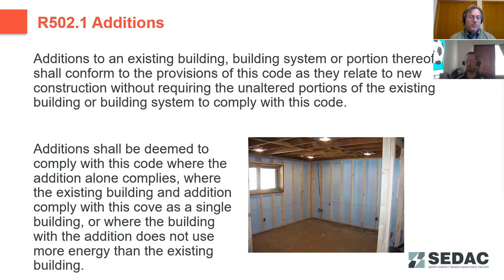You can do prescriptive compliance for the addition and test it independently, as far as meeting R-value requirements, making sure the envelope is sealed, making sure any new ductwork is sealed. But again, additions to existing structures do not have a requirement for air leakage testing or duct leakage testing, the duct leakage testing being an Illinois amendment.